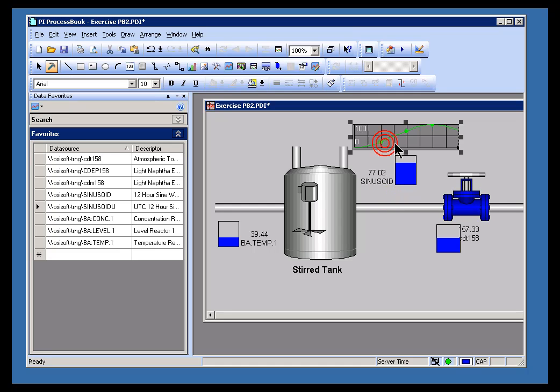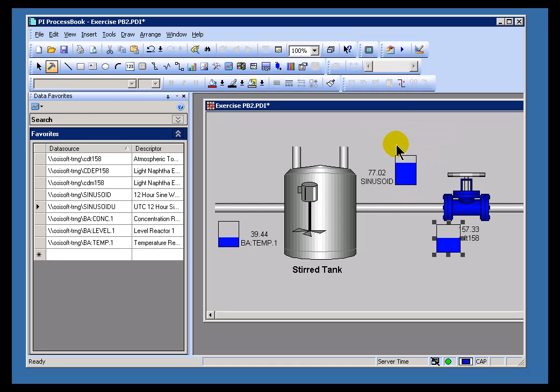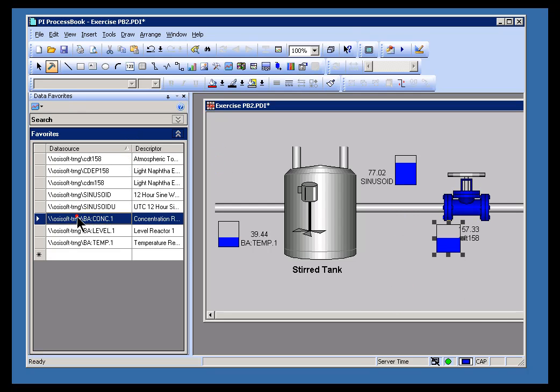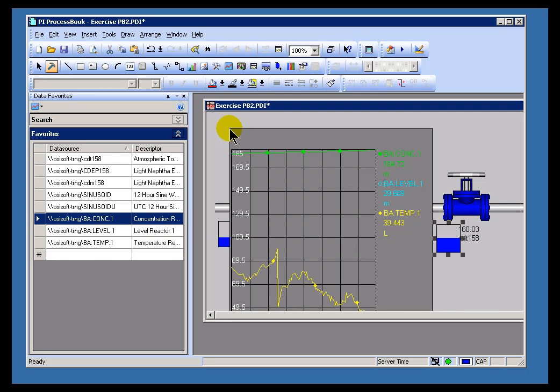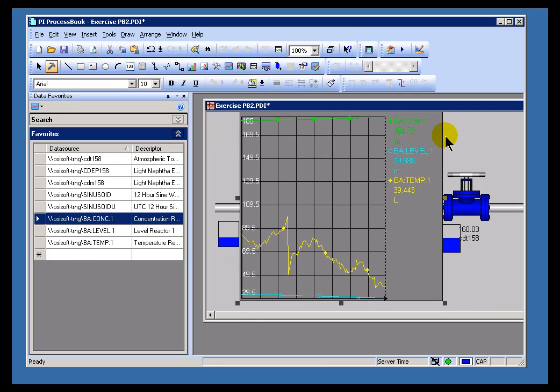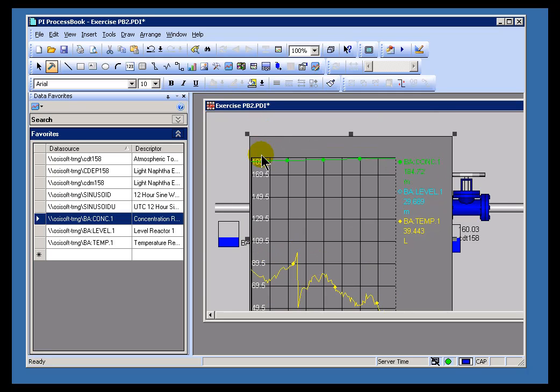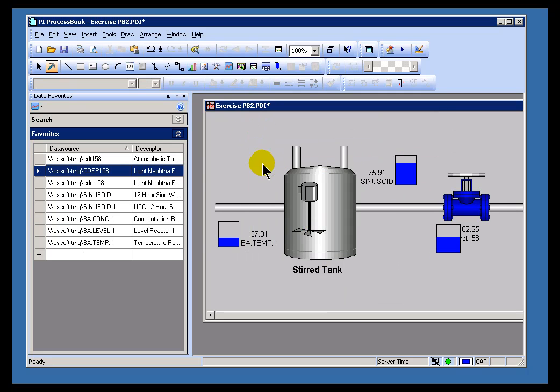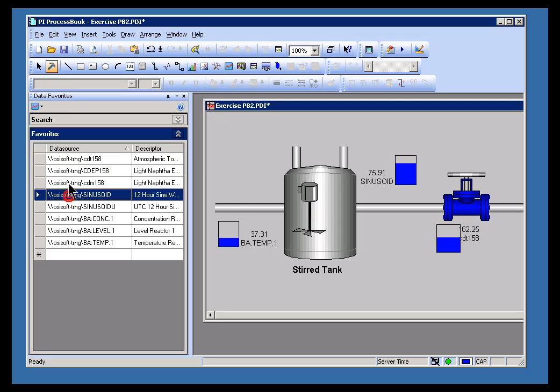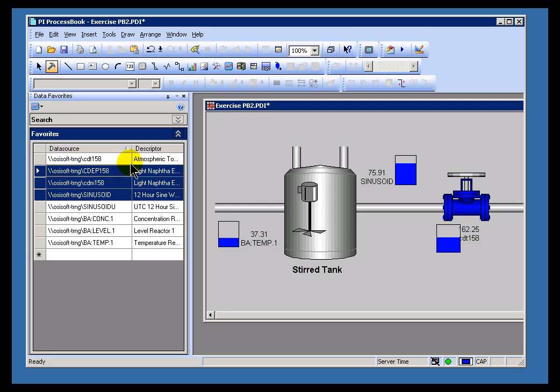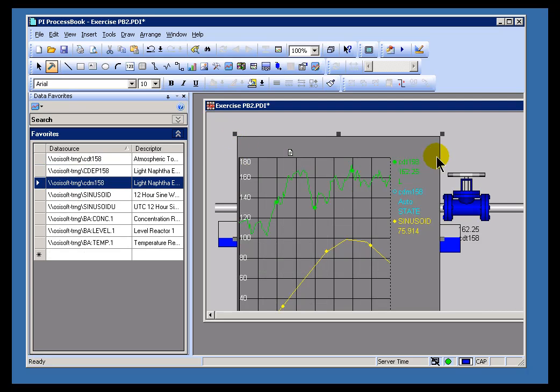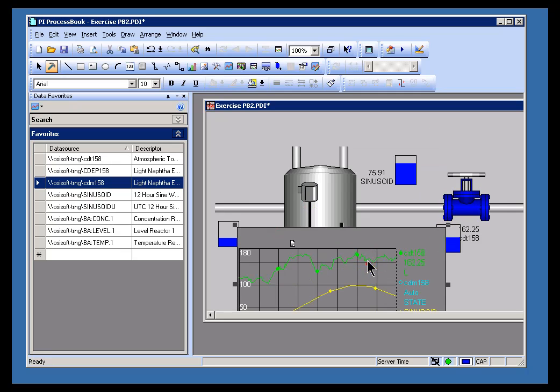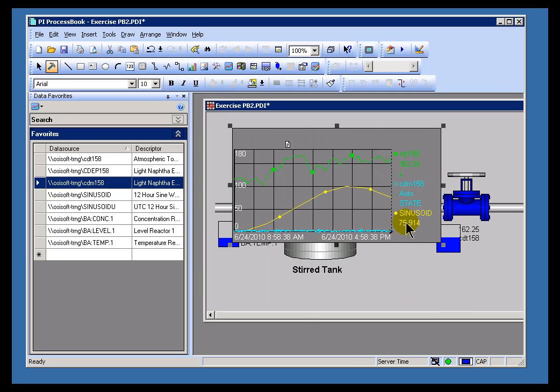Now, one last feature that we haven't exploited yet is what happens if you choose two things at once. If you choose two of these and then generate a trend, or more. Well, as you can see, when I do that, it's simply going to go ahead and build as many traces onto that trend as what you've selected. Again, let me demonstrate that again. I can pick any of these and just drag them over and what you'll notice is it builds a trend that has multiple values on it and you can always add more.